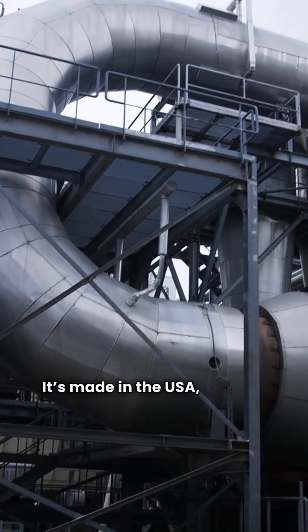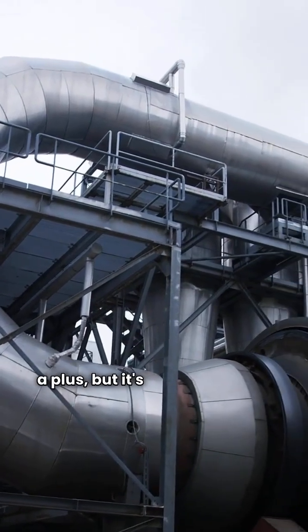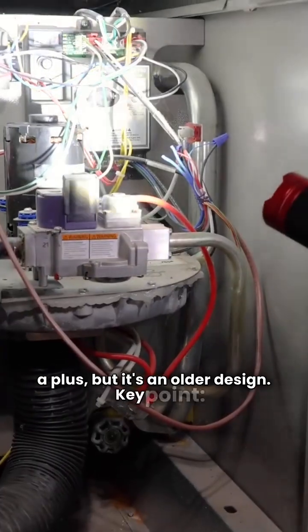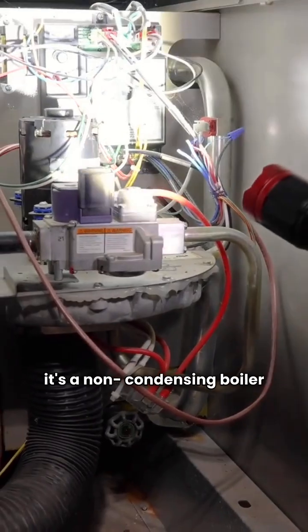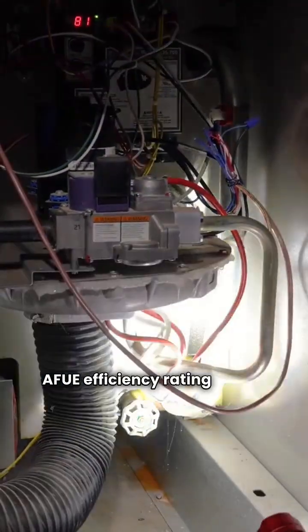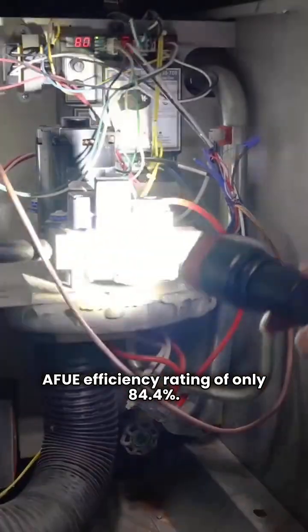It's made in the USA, which is a plus, but it's an older design. Key point, it's a non-condensing boiler with an AFUE efficiency rating of only 84.4%. This model uses atmospheric combustion. What that means is it pulls air from inside your home for burning the gas.